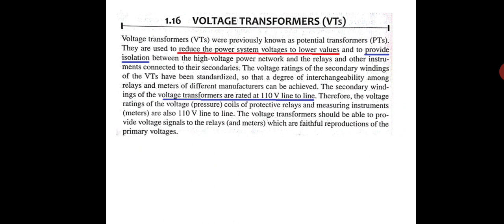Voltage transformer. So the voltage transformer will read the voltage of your line to be protected, and it does it with the help of a potential transformer. How does it happen? It will step down the voltage. In the primary side, a high voltage is connected, high voltage is applied at the primary winding, whereas in the secondary side, the voltage is stepped down and connected to a voltmeter. The voltmeter will measure this low voltage and give this measured voltage to the relay circuit.